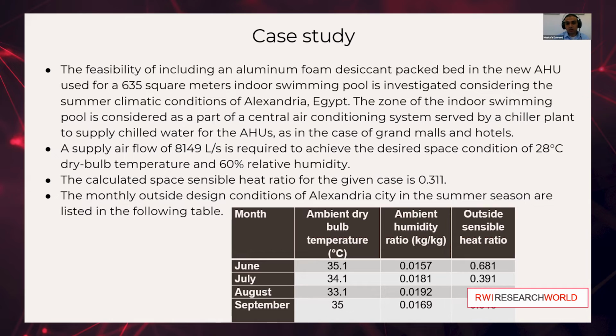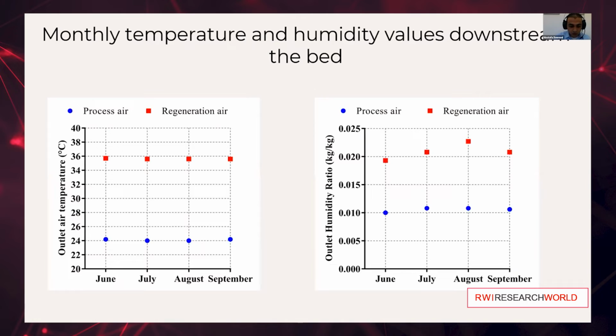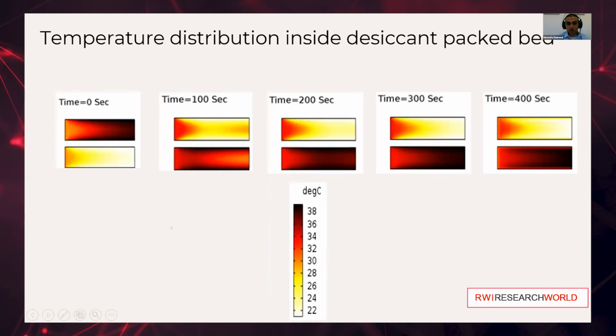The monthly outside design conditions of the city of Alexandria for 4 months of summer are listed in the following table, and it shows that August is the highest latent load month. 4 case studies for the city of Alexandria were conducted at a cycle time of 800 seconds. Results of downstream values of the dehumidification bed show that there is a very slight variance in outlet air temperature and outlet air humidity over the 4 months. This is due to the dependence of the dehumidification bed on upstream air at mixing conditions, as shown in the previous figure.